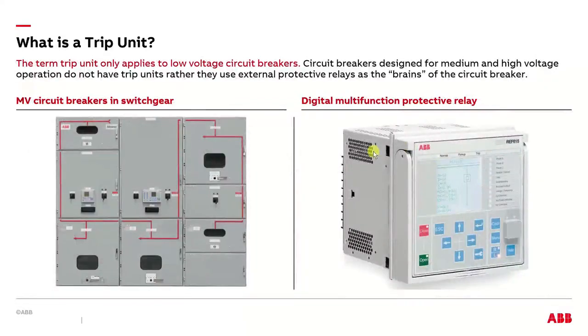Now here's, and this is interesting, and I always kind of like the history of how these things came about, but the trip unit term only applies to low voltage circuit breakers. When you get into circuit breakers that are in the medium voltage and high voltage range, they don't have integral trip units. So you buy the circuit breaker and it's just a switch. So you have to also specify the relay that acts like the trip unit, but they're separate components and you specify them separately. They're ordered separately. They can be from different manufacturers.